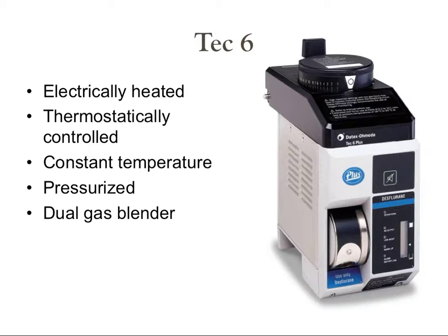The Tec 6 is the vaporizer for desflurane, and this one is special. It's electrically heated, thermostatically controlled at a constant temperature, pressurized, and it's a dual gas blender.